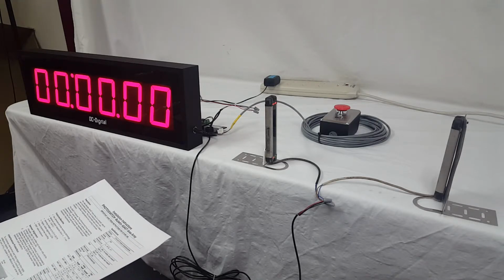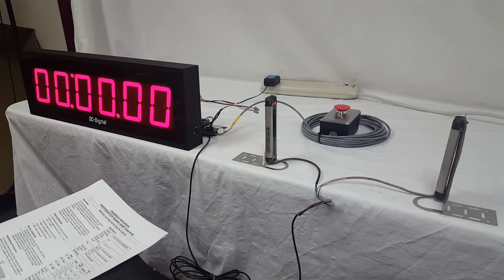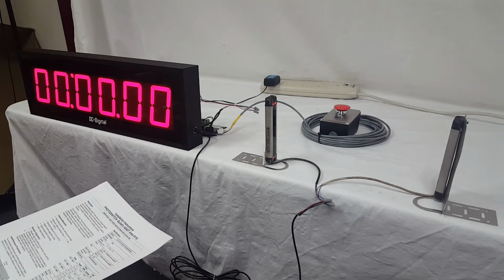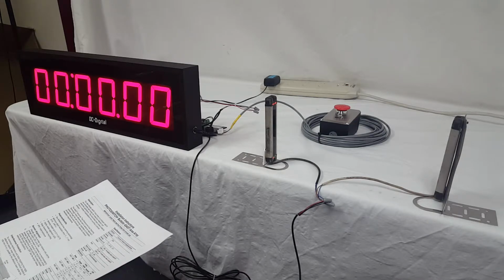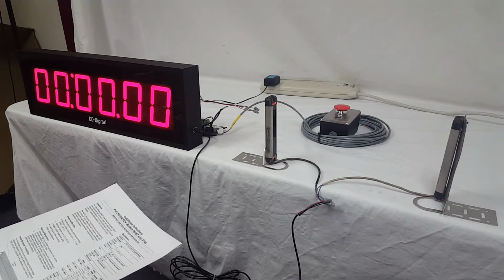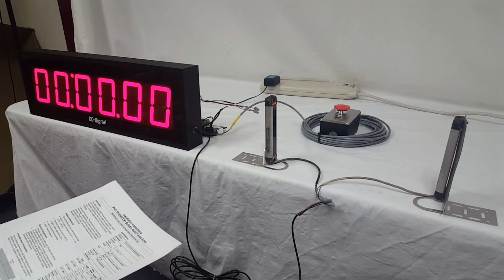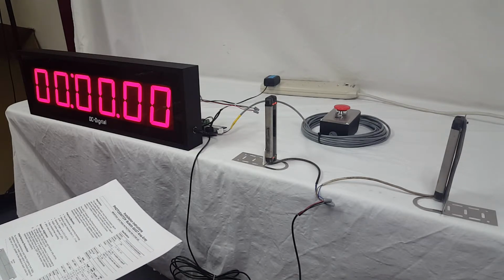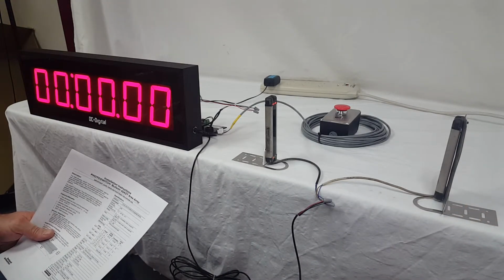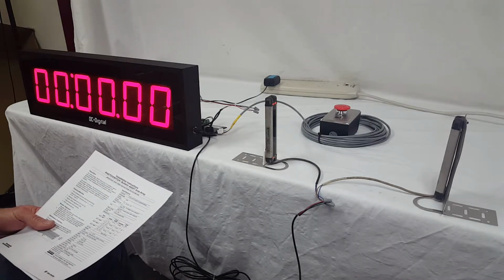It has two-dimensional array scanning technology, which allows the user to sense an object as it passes through the pair of arrays regardless of orientation, provided the one axial dimension meets the minimum resolution. Minimum resolution is 0.43 to 0.66 inches high, I'm supposing. Sensing range is up to 2.5 meters wide, so you can go up to 8 feet between these two, and it will scan approximately a half inch is what I'm looking at.